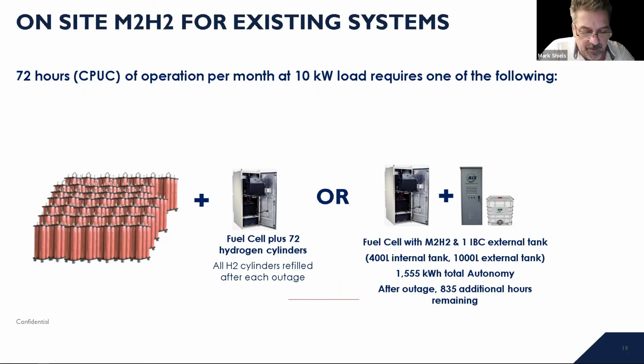So a lot of the BTSs where these fuel cells with hydrogen bottles are actually on rooftops, simply using high pressure hydrogen with fuel cells because they can't put diesel generators on these rooftops. They have issues with noise and vibration and community complaining. So they used to use 1 or 2 hydrogen vessels, and that would keep the fuel cell going for maybe 4 to 6 hours. But now they have to keep it going for 72 hours.